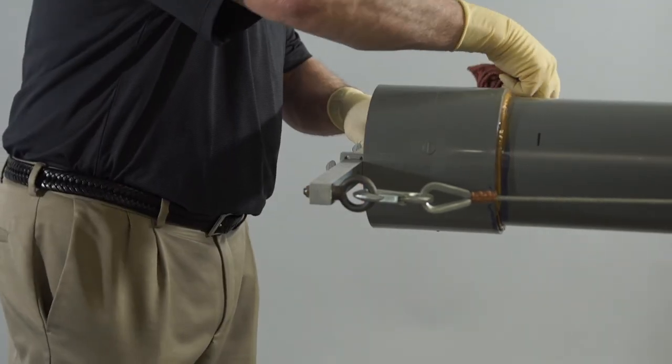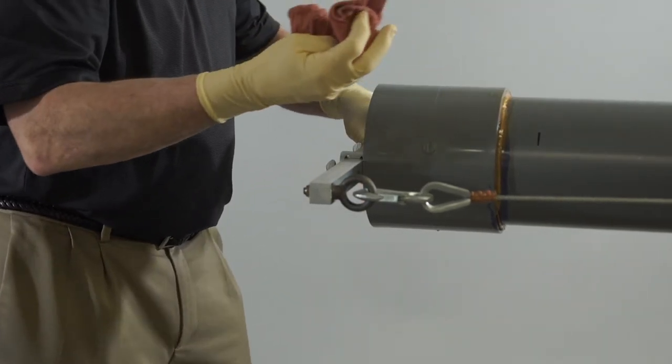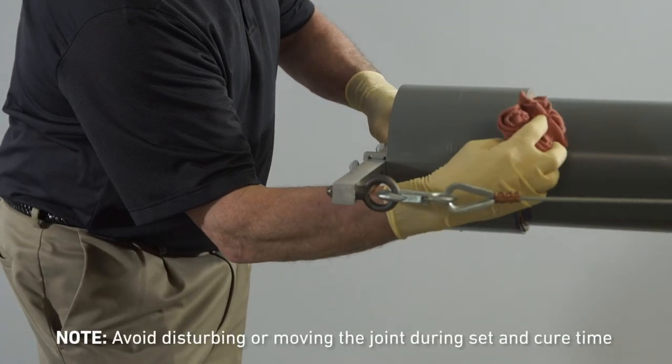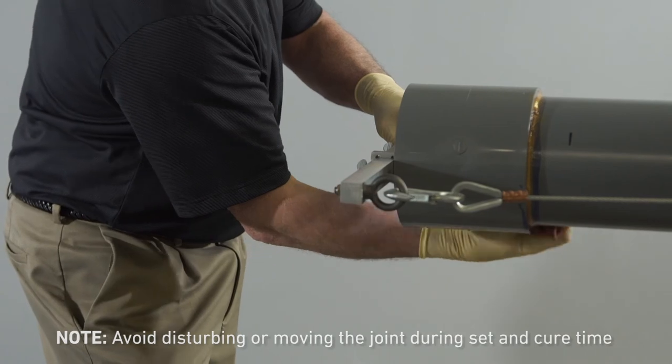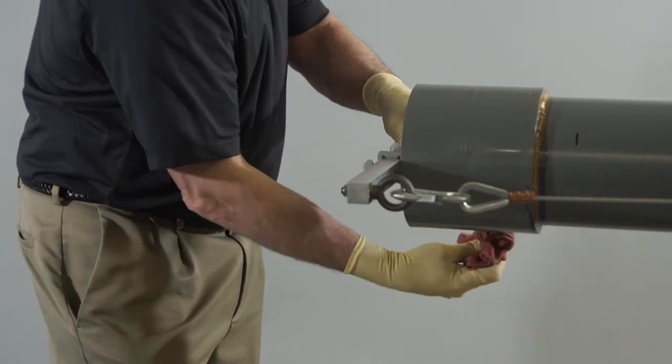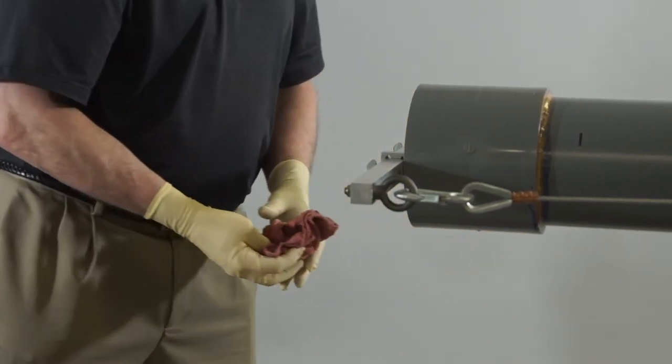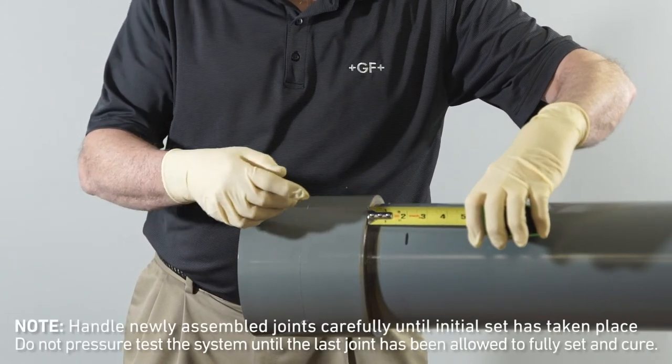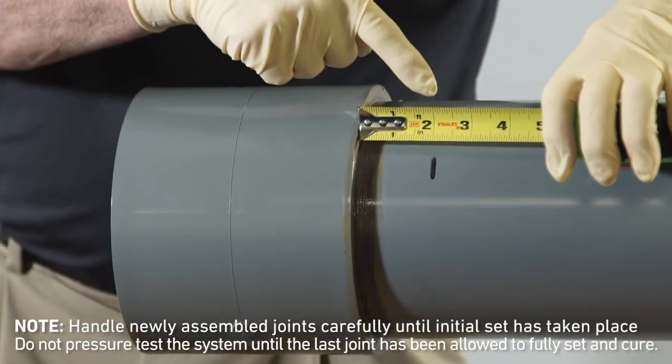Using a clean dry rag, remove the excess solvent cement from the pipe and fitting, including the ring or bead around the socket entrance. Excess solvent cement does not strengthen the joint. To ensure the pipe is fully inserted into the fitting socket, measure the distance between the second mark on the pipe and the lip of the fitting. The measurement should be 2 inches.